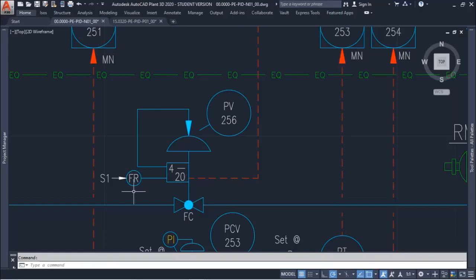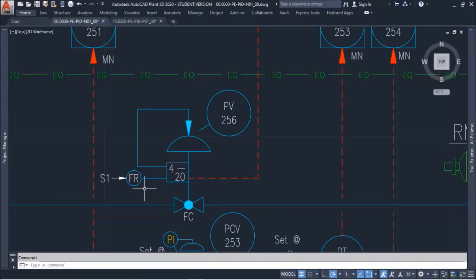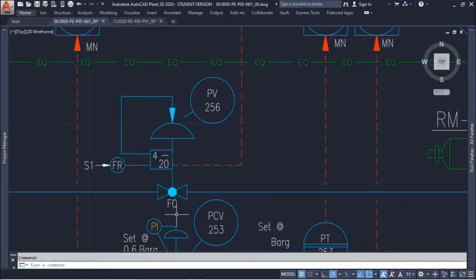Here we have the indication of the instrument air and the filter regulator, which means the instrument air is at a pressure higher than allowable for the control valve actuator. Because of that, we need a filter regulator. We also have information about the fail safe position of the valve.